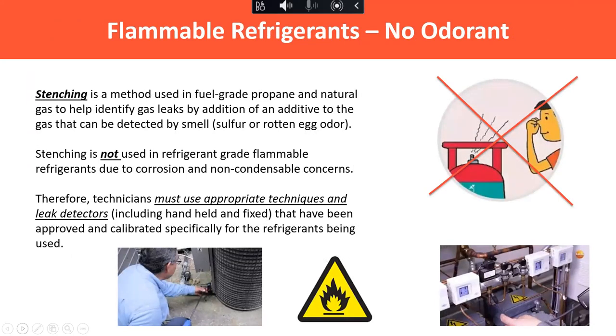This next one is important to point out: there's no odorant or stenching agent. If you're familiar with fuel grade propane, whether for your gas grill or natural gas into your house, sulfur compounds are added to give it a scent. That's not the case with refrigerant grade flammable refrigerants, even propane or the A2Ls. Those organic compounds won't survive long term inside equipment that's being pressure cycled and temperature cycled over and over—they tend to break down and cause system problems. So we're not going to be relying on our nose as a leak detector here, which is good because your nose isn't really calibrated. It's important to point out that our traditional handheld leak detectors and area monitors are going to be very important going forward.